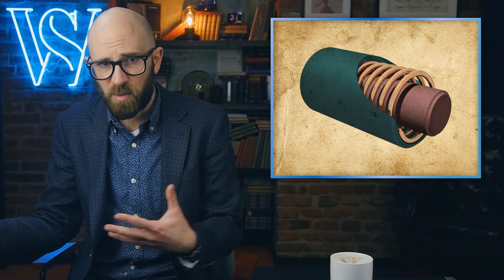During these fluctuations in magnetic field, the ballast's core is physically squeezed and released in a process called magnetostriction that, at a frequency of either 100 or 120 Hz, produces that infamous buzz.